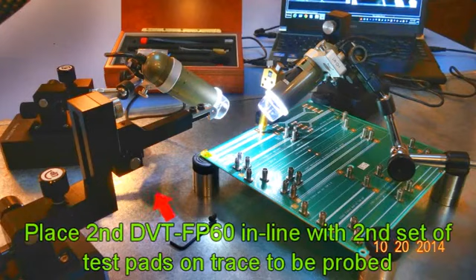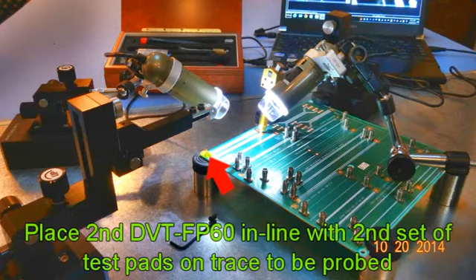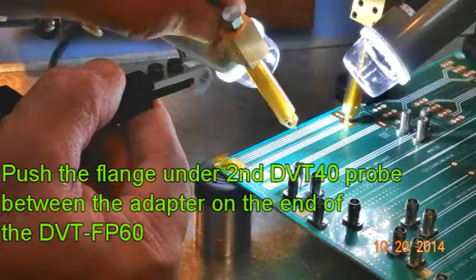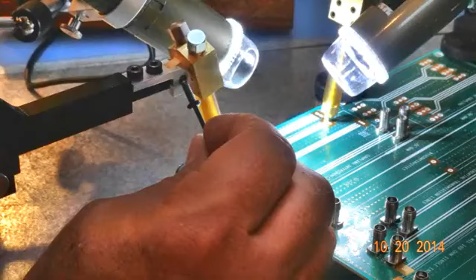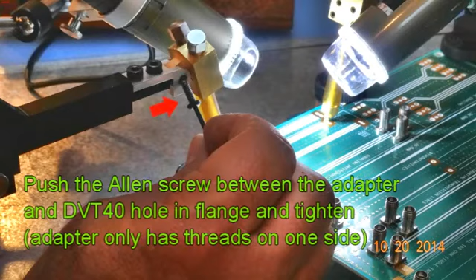Next, place the second DVT FP60 in line with the second set of test pads on the traces to be probed. Take out the second DVT40 GigaProbes and remove the protective plastic cover. Remember, keep these plastic covers on the probes to prevent them from being damaged when the probes are not in use. Next, push the flange under the second DVT40 probe between the adapter on the end of the DVT FP60. To secure the DVT40 probe to the adapter, push the Allen screw between the adapter and the DVT40 hole in the flange and tighten.